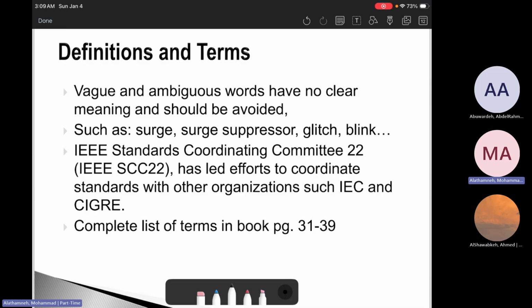So I would say a surge arrestor is only designed for transients, like lightning strikes, while it will not help when there is a sag or voltage drop. It will not help with harmonics, because if there are harmonics, we need to use a filter or load redesign to solve this.